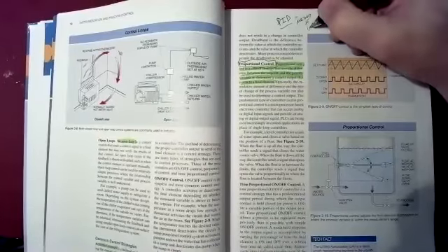This tank has got something that attaches at the top and then at the bottom. This little symbol here that looks like a bow tie, that is a classic manual valve symbol. It shows me a number on there, 1 inch, so that's a 1-inch valve. It shows me a line leading up to a little circle. That little circle has very specific meaning. In this diagram, that circle means that there's some sort of instrument there. And each code in that instrument means something. And there's usually a 2-letter code, sometimes 3-letter code that tells me what that instrument is.